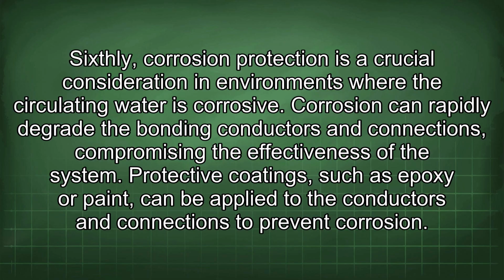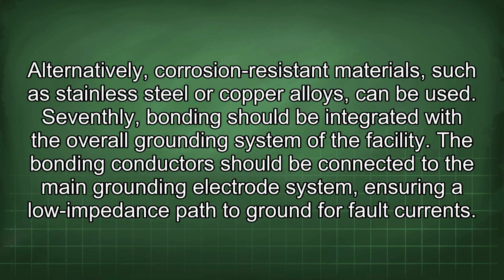Sixthly, corrosion protection is a crucial consideration in environments where the circulating water is corrosive. Corrosion can rapidly degrade the bonding conductors and connections, compromising the effectiveness of the system. Protective coatings, such as epoxy or paint, can be applied to the conductors and connections to prevent corrosion. Alternatively, corrosion-resistant materials, such as stainless steel or copper alloys, can be used.